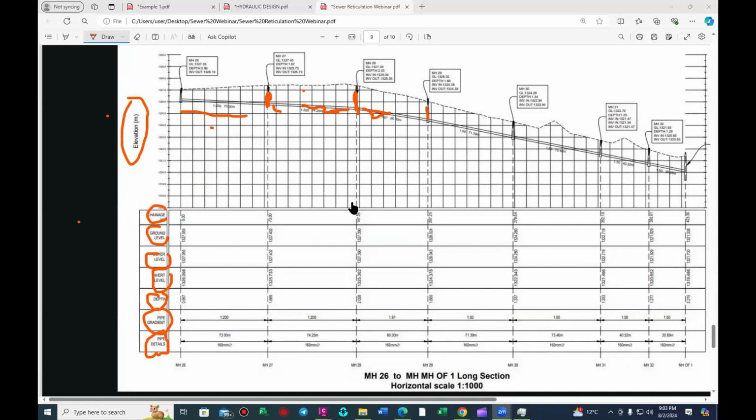Let's see. All right. Do you redesign using slope as per recommended pipe diameter? Yes, that's what you do. We said it's an iterative process. What is the roughness of the pipe? According to the code required, we use 0.6. So you're given the roughness of that pipe. For your Manning's, it's 0.006. For Colebrook, it's 0.6, right?